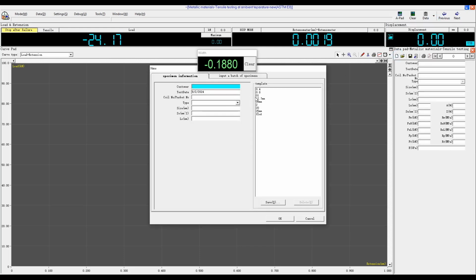First, select a test standard, in this case ASTM E8. Then click New to input the sample information. The sample type for round specimens is indicated as circle. The flat specimens are indicated as flat. When selecting your specimen type, be sure to include the diameter details for round specimens and the thickness details for flat specimens.